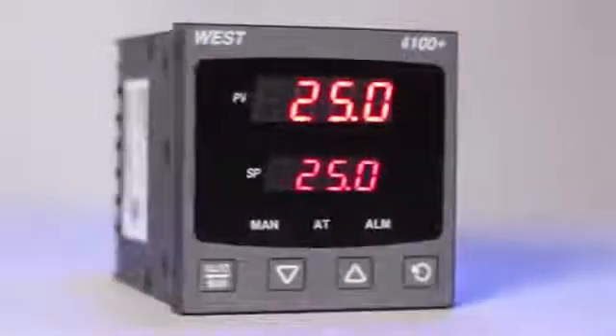In fact, if you see the process oscillating over the same time period as the cycle time, it's a good indication that you set the cycle time too long.